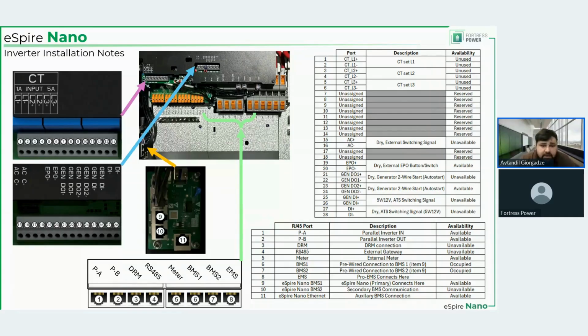Meter, external gateway, that is available, obviously. That is for that meter that has the CTs connected to it. And we're going to see how in a moment. Port 6, or item 6 and 7, BMS1 and BMS2. They are pre-wired and they are connected to item number 10 and item number 9 from the factory. And that's where you connect the Nano BMS communication cable. And number 8 is Pro EMS. If you have Pro package, port number 8 is the one to be used.